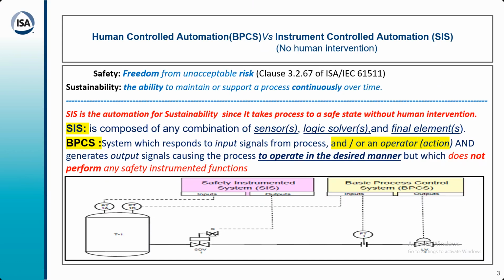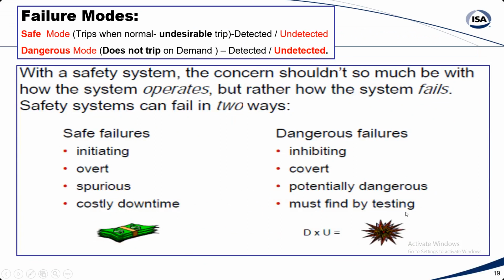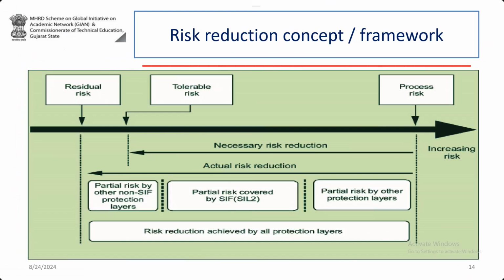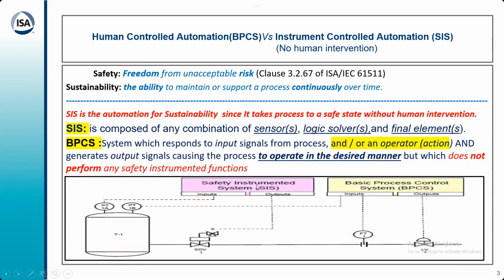It may not work. So the only way to find out the dangerous failure is you must test it. Every SIS system, every SIF system needs periodic testing, which is known as proof testing. Dangerous mode undetected, safe mode undetected, detected: if dangerous mode failures are happening in the SIS, you need to periodically test it. So this SIS is a dormant and passive system. BPCS is an active and dynamic system. The control valve is dynamically moving. This is the basic difference.